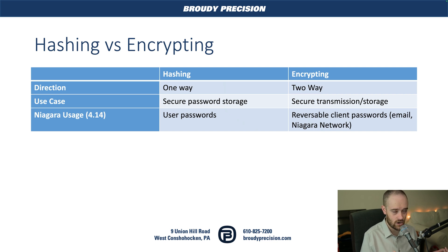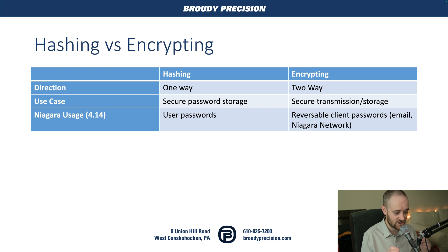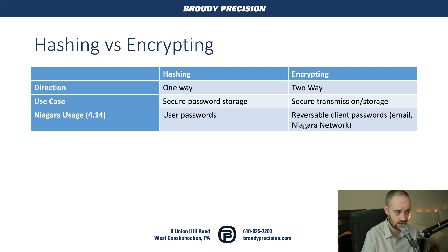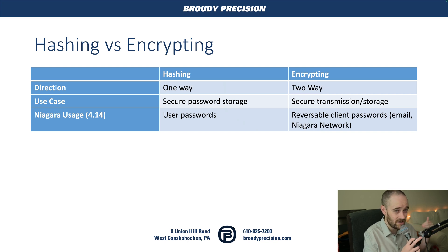That's the way our user passwords are stored in Niagara. When you first set up a user, it goes through the hashing algorithm and saves the password. Every time the user goes to log in, the hashing algorithm is run against the password that was entered and then compared with what's saved in our station. That's what's used for our user passwords because we don't need to recover the password or specifically use it in the station itself.